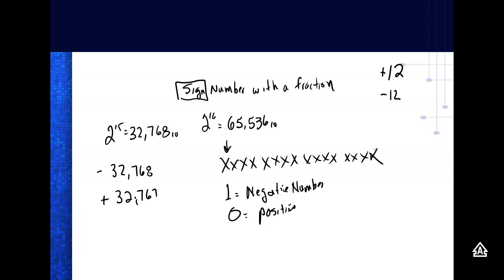So timers can't count backwards. They can only count forward, right? Understand? So that means the maximum number you can put into the preset register of an RSLogix 500 timer is 32,767. If you go past that number, it'll change signs and it won't work. Everybody understand that? It uses something called two's complement, which is really cool, to represent signed numbers. But that's what we do, basically, just sacrifice the most significant bit.